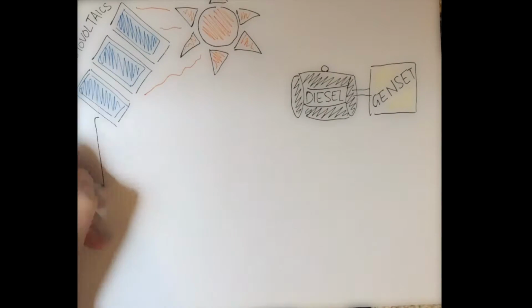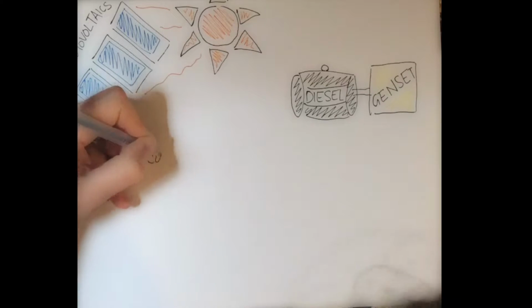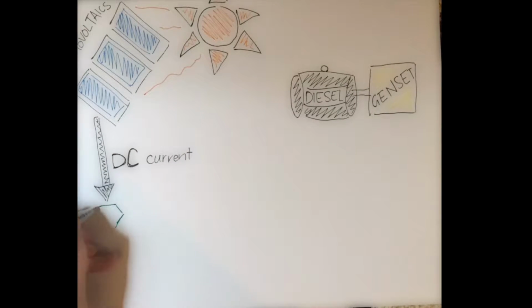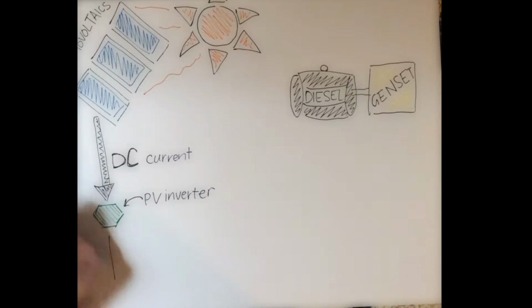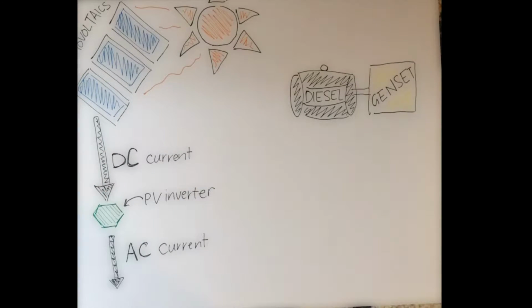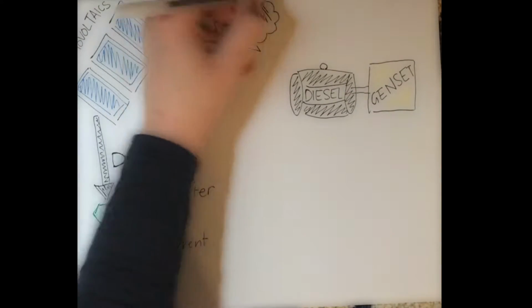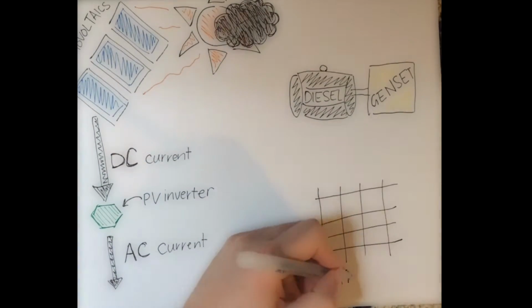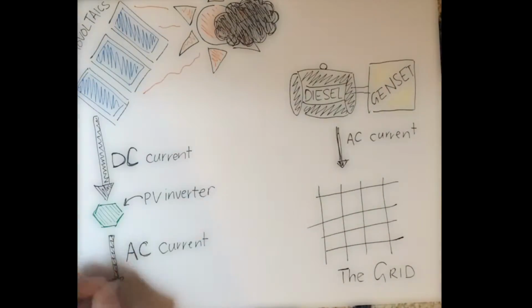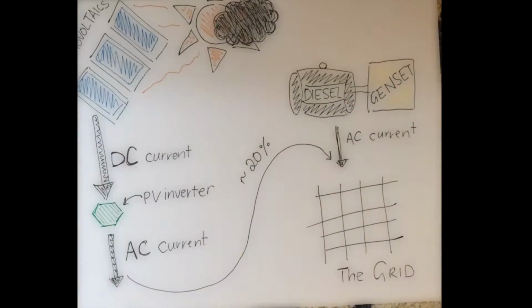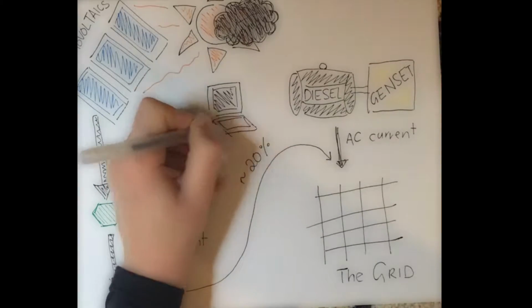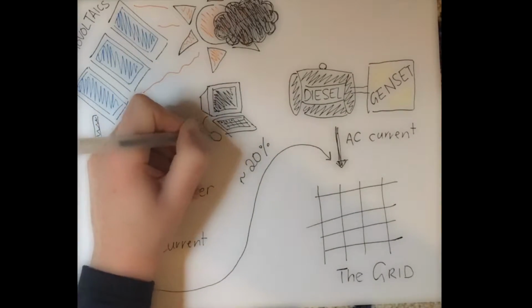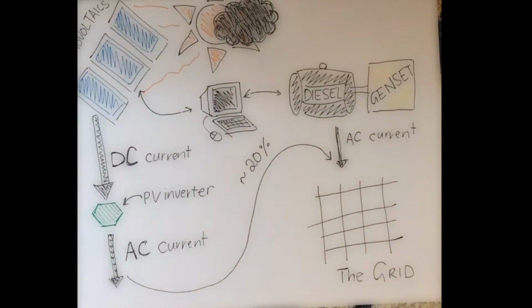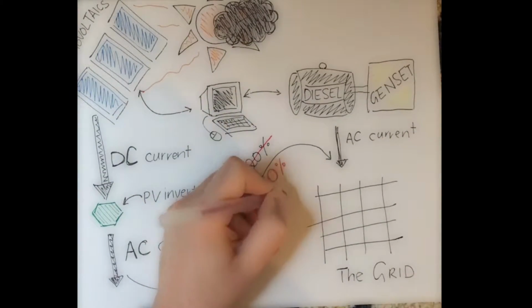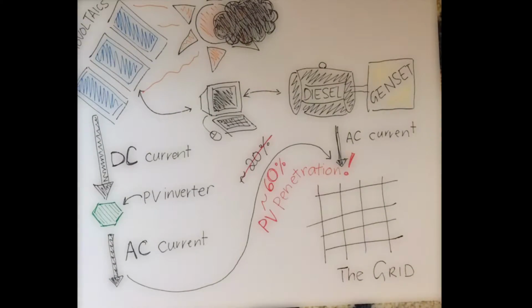In a photovoltaic system, PV modules turn sunlight into DC current. This is transformed into AC grid current by photovoltaic inverters. Because of the fluctuation in irradiation, the proportion of PV power that can be fed into a diesel grid, also known as the photovoltaic penetration, is normally about 20%. In order to achieve a higher share of photovoltaics and increase savings, smart communication is needed between the PVs and the gensets, enabling up to 60% penetration with maximum grid stability.